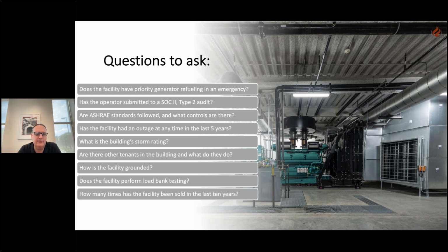What kind of tests do they do? You never want anything to be a surprise. So you can do something called a load bank test, where you're really simulating a complete failure of electrical power. In a tier 3 facility, you're not impacting availability, you're not creating risk for users, but you're really testing out operations and the preventative maintenance you've done on your generation and UPS gear and cooling to make sure that the data center can continue to operate in an emergency.